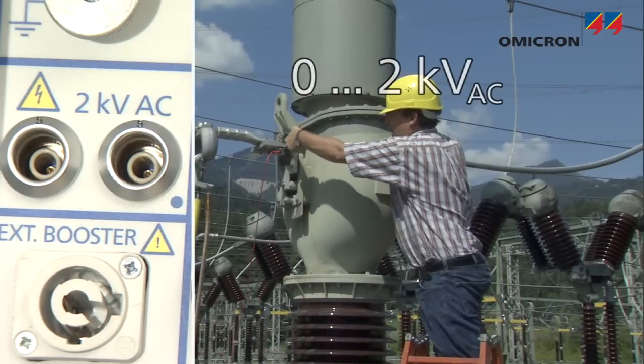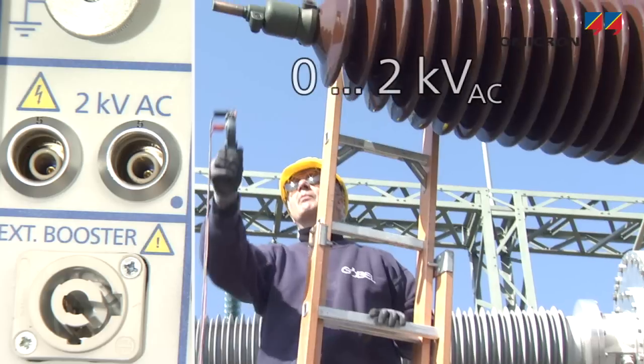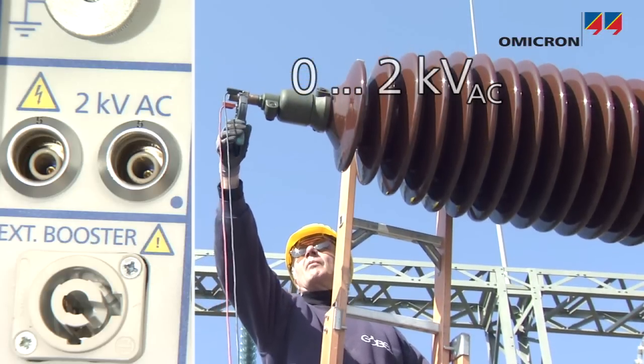Its high voltage output generates up to 2000 volts and is used to record a CT's magnetization curve, test a VT, or perform transformer ratio measurements.